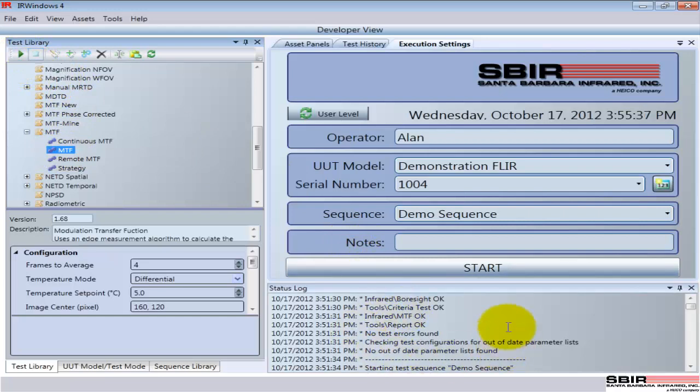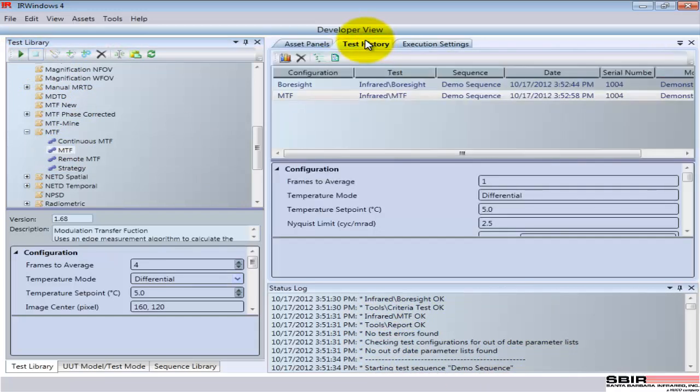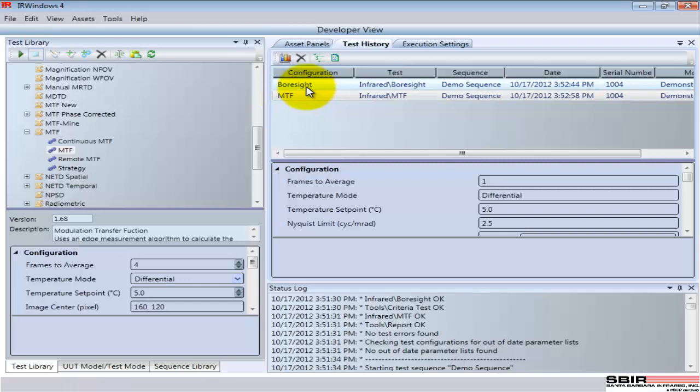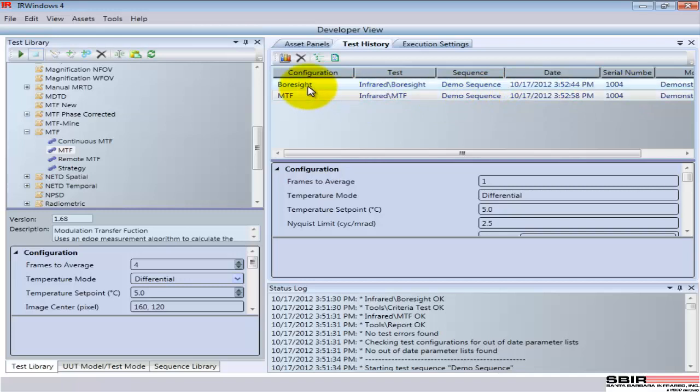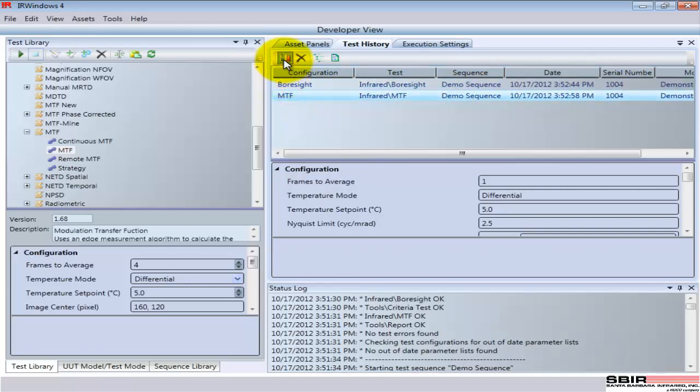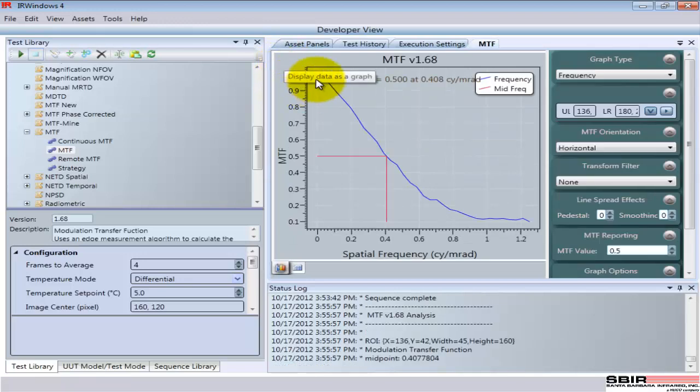We have the status while the test is being run, and when it's complete, it stores all of the information about that test in the test history, which is a database of results. So what you see here are the two tests that were run earlier on this particular device, serial number 1004, what we just ran, and here's the boresight result and the MTF result, and I can come in and take a look at those results in more detail.